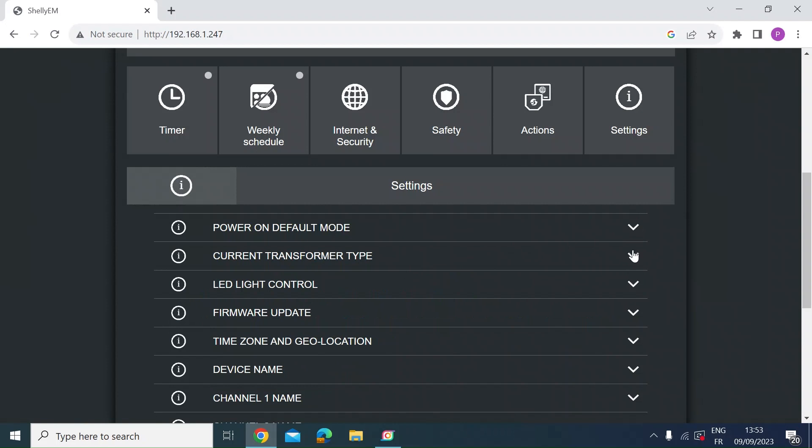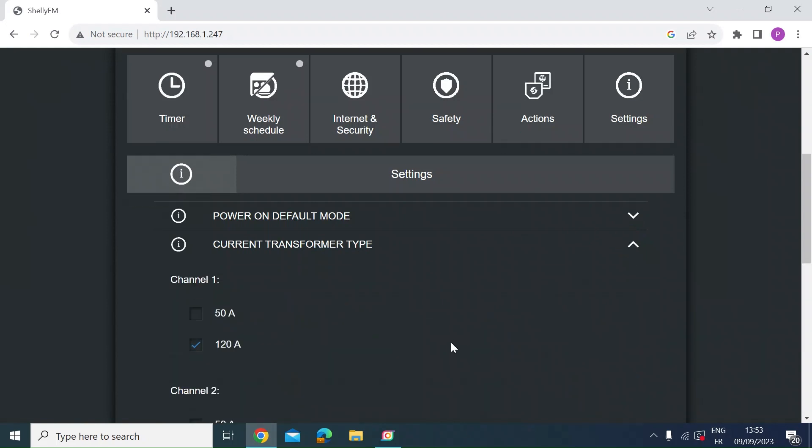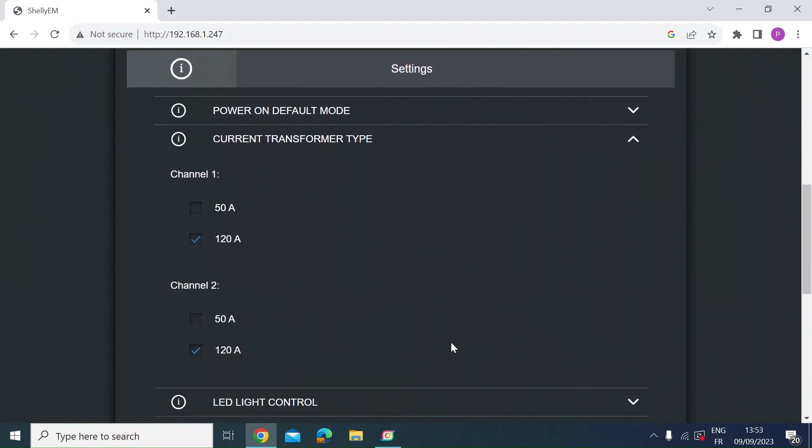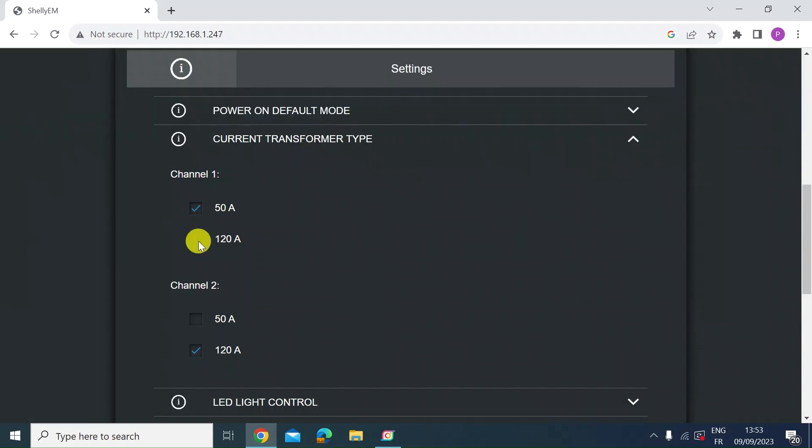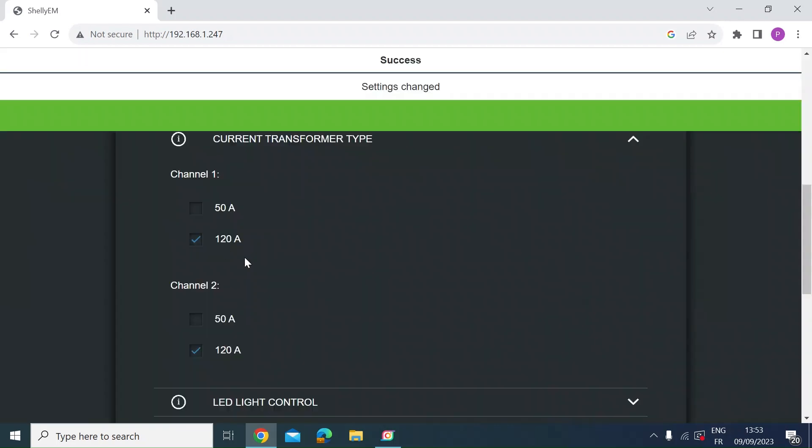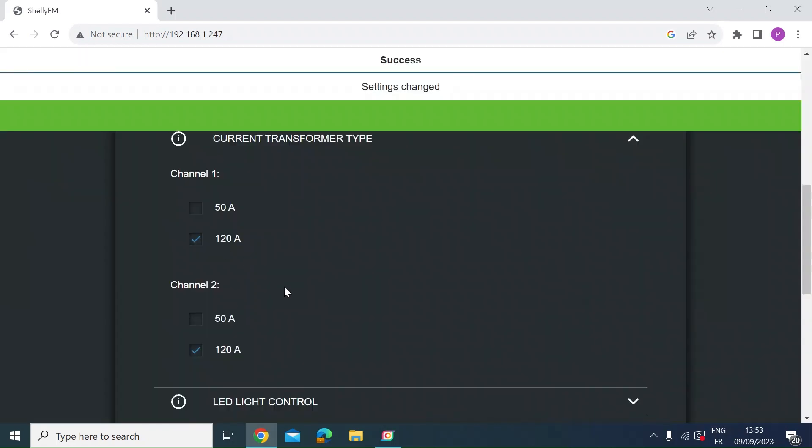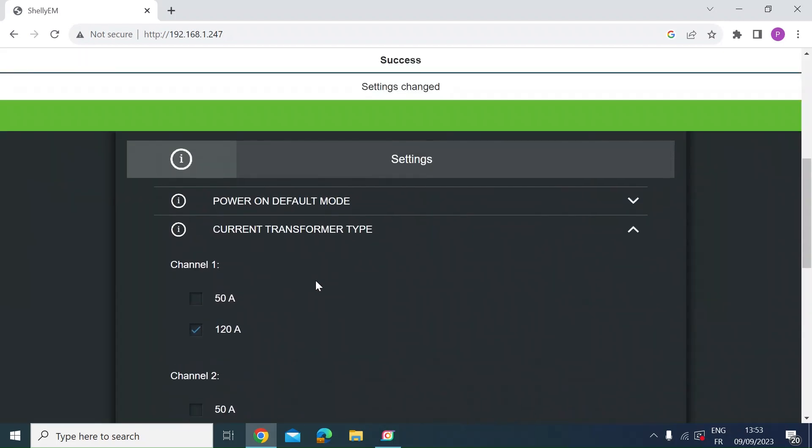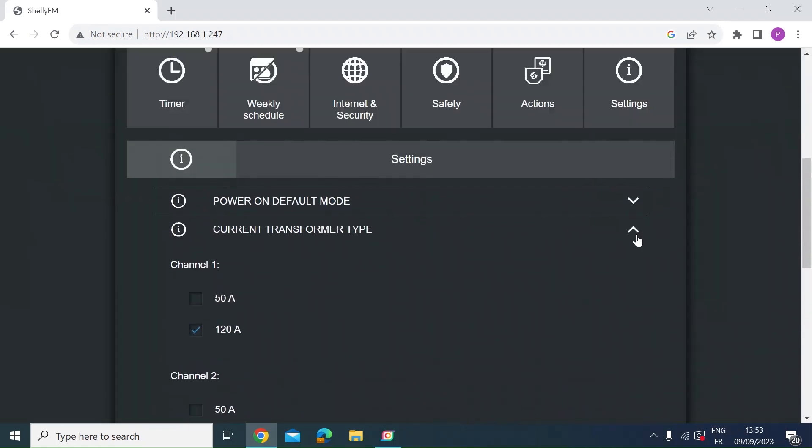The current transformer type. So this is two channels. I'm measuring 100 amp rated meter tails to both of my consumer units. So I got the 120 amp transformers. So you just enable which one of these you want to use. If you've got a smaller one go for 50 amp. I've got the bigger one so 120.